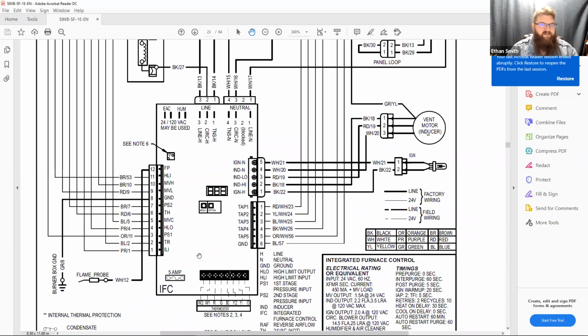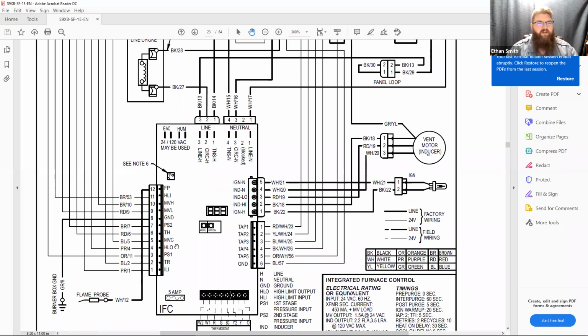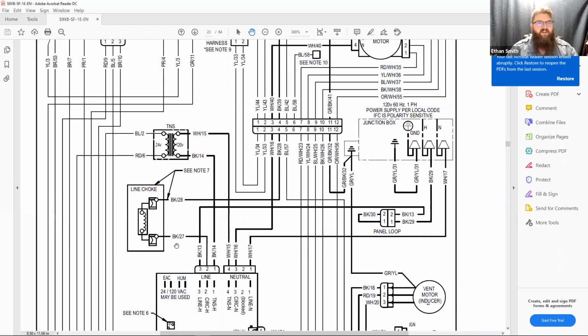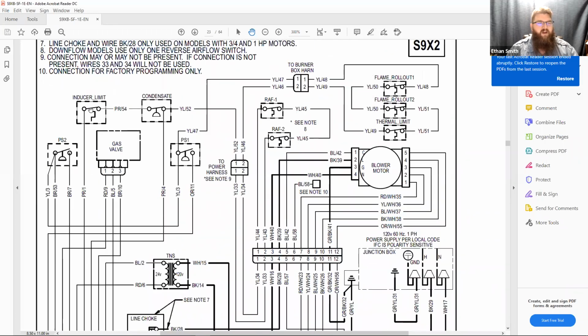So the first thing that happens in a furnace is it's going to go out and check all its safeties. So we should be able to come out here to all of our safety devices. Okay, my limits, my condensate switches, all my flame rollouts. Okay, they're all going to be energized. Okay, and it's really handy that they've given us a junction up here. So we've got a little plug, and we can actually check for voltage across this plug, because it's going to go out and go through all of these for us. So it allows us to shortcut that.